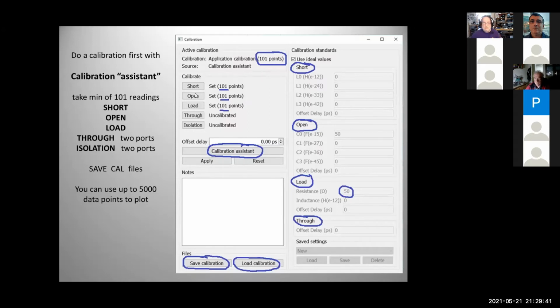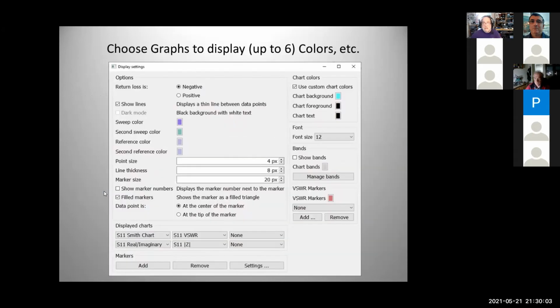I use the computer. You can calibrate it with a short, open, and load, and also the through, to go with 2 ports and an isolation. So most of my calibration files are about 5,000 data points. So it's maybe a 100K file, and it takes maybe less than 1 minute to do my calibration. Then I save it. It can display all kinds.